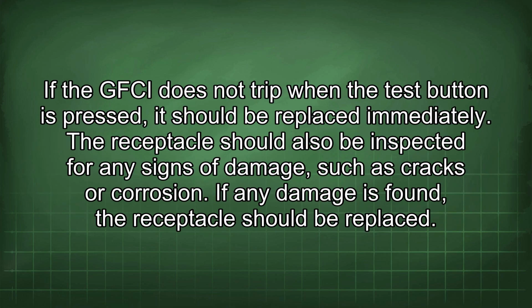If the GFCI does not trip when the test button is pressed, it should be replaced immediately. The receptacle should also be inspected for any signs of damage, such as cracks or corrosion. If any damage is found, the receptacle should be replaced.